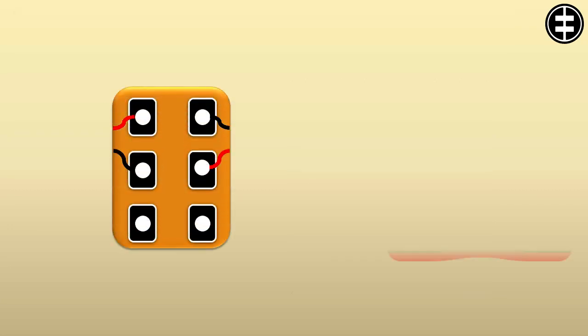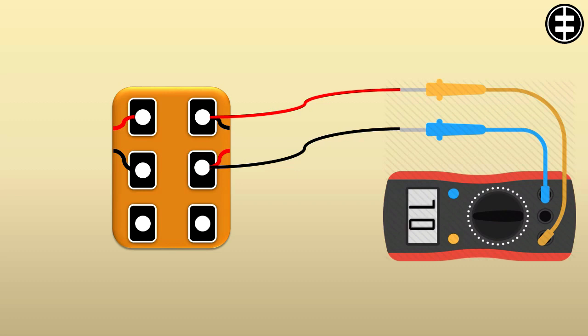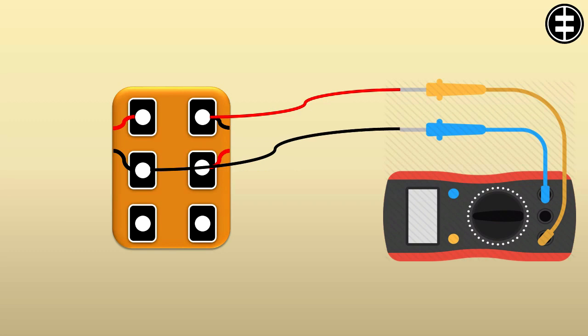Now using the multimeter on ohm meter position, check any 2 leads. If the measurement was open loop, that means these 2 wires are not related to the same winding. Recheck until identifying each winding's 2 leads and check each winding ohm value.